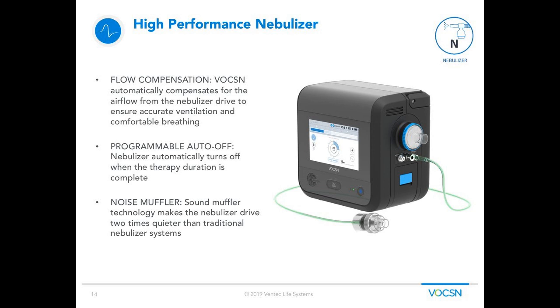What happens to the ventilator during this period? The ventilator is alarming, giving you all these nuisance high pressure alarms. Some ventilators have a nebulizer mode you can put it into. All that does is suppress the alarms and widen out the alarm parameters. So the patient or the person on the ventilator is still feeling all of that high pressure.